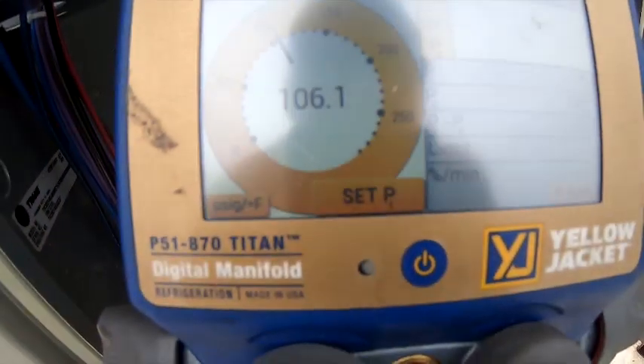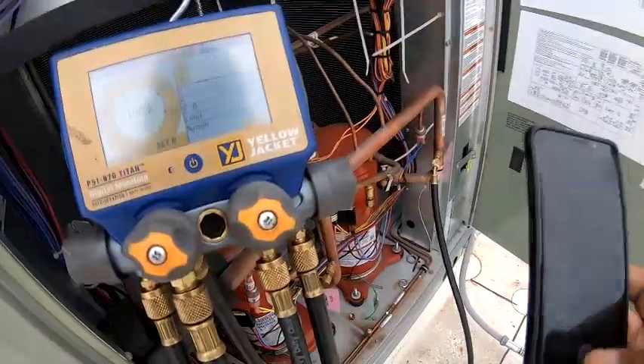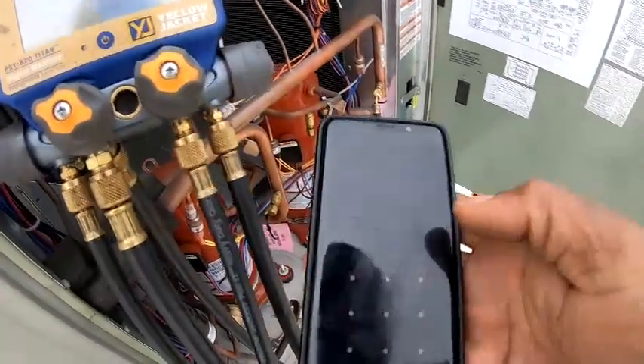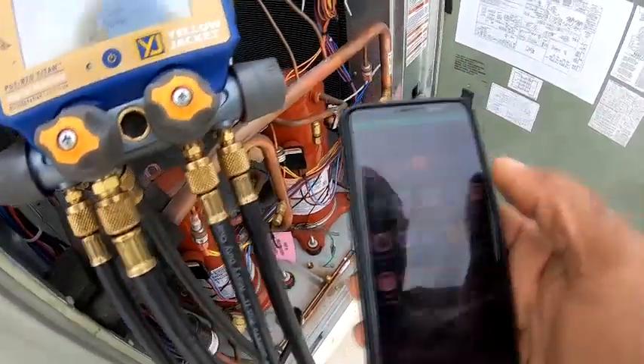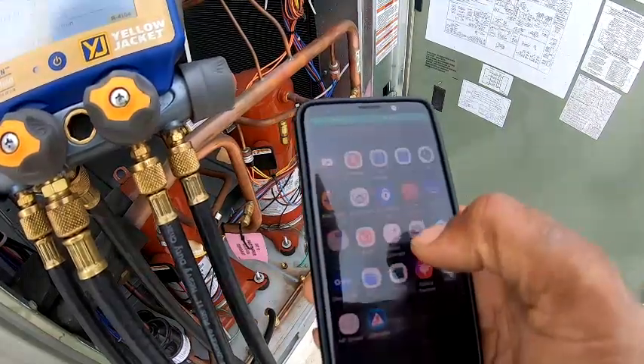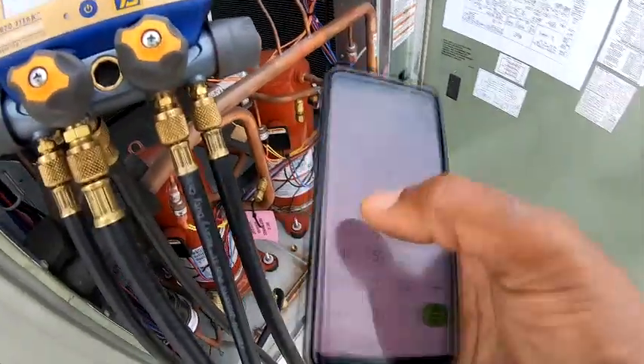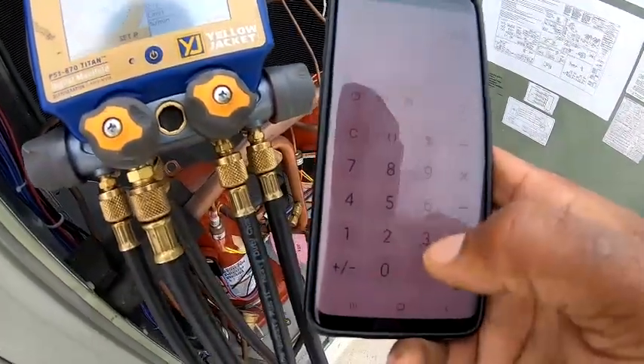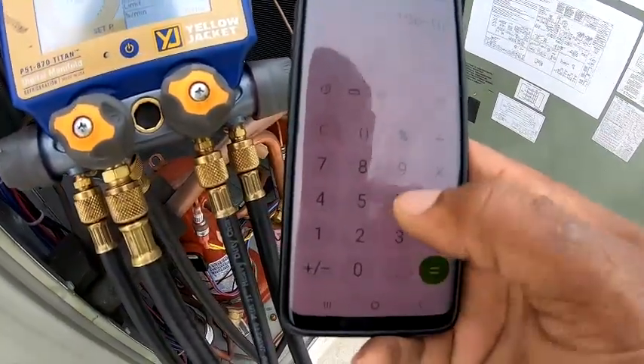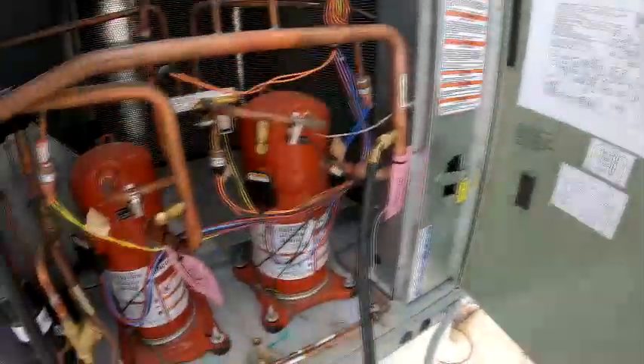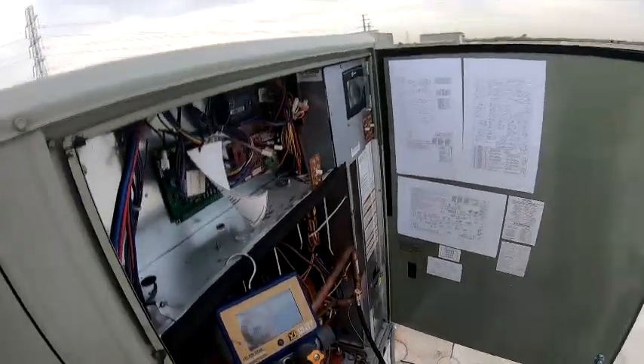And we're gonna continue. So now it's doing a pressure hold. Now I can go to my calculator right here. Let's say I got 106 in there, we'll do the calculation. So if I got 106 take away 0.6%, it shouldn't go below 105.36. So like I say, that's one way to do a leak search, put nitrogen in there.